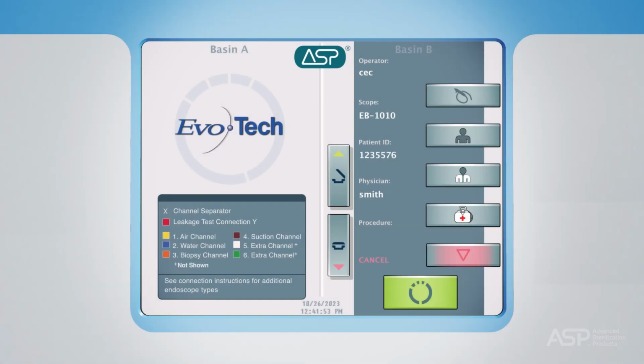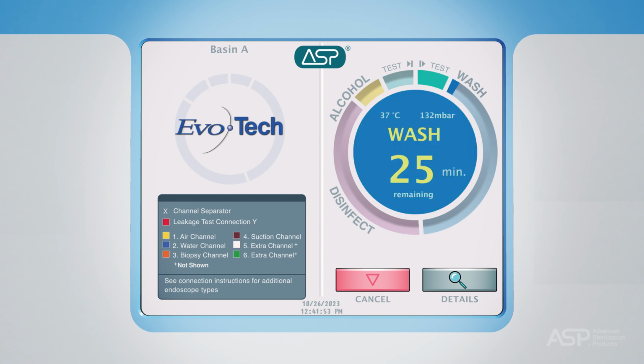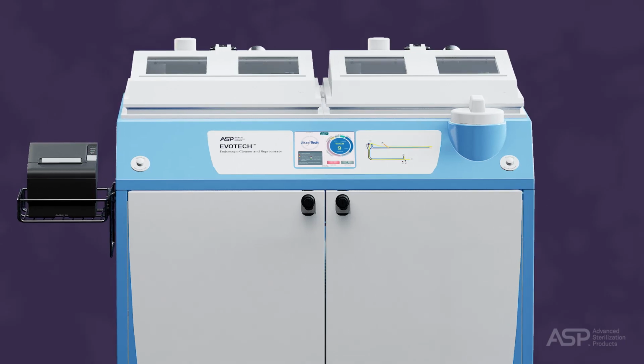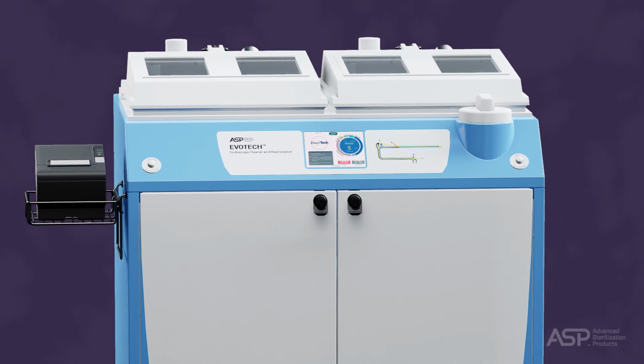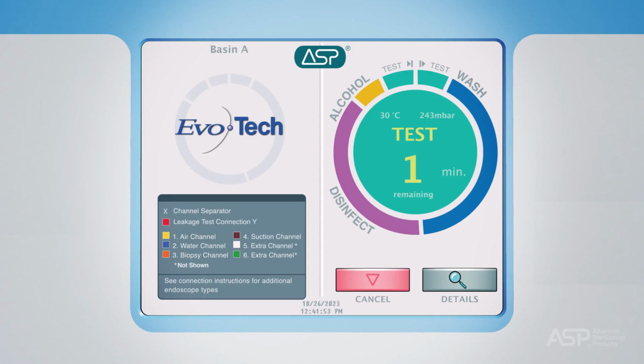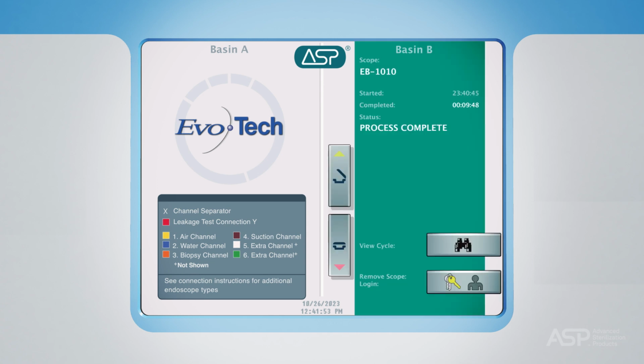A leak test is performed in the EVOTECH ECR at the beginning of the cycle to check for large leaks that would prevent the endoscope from being reprocessed and is necessary prior to the endoscope coming into contact with water. The endoscope is pressurized throughout the cycle to prevent invasion of liquid. Just prior to the end of the cycle, the endoscope is again checked for leaks.